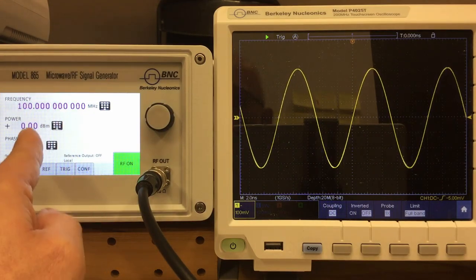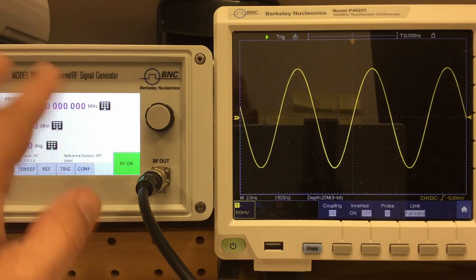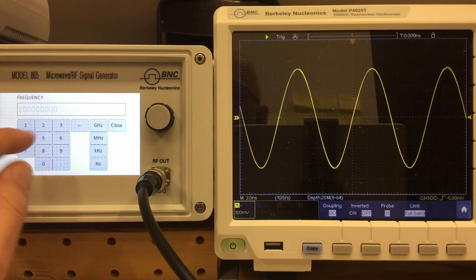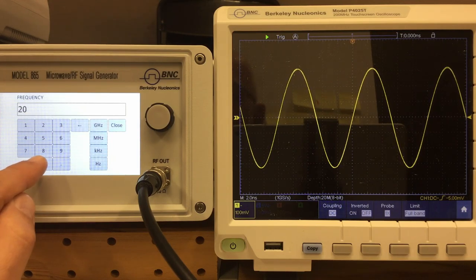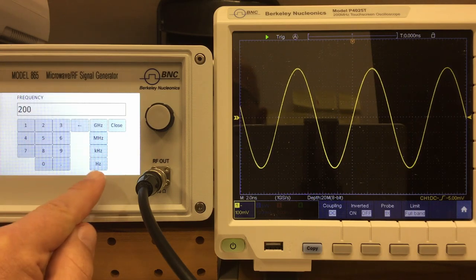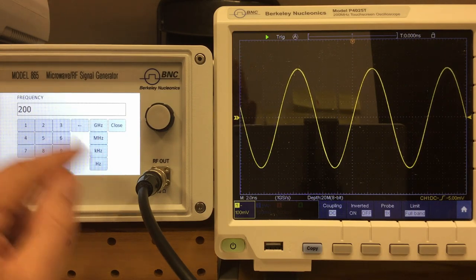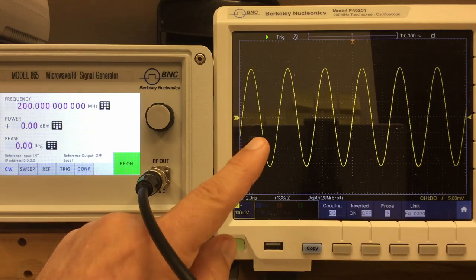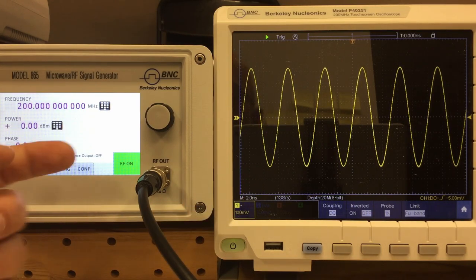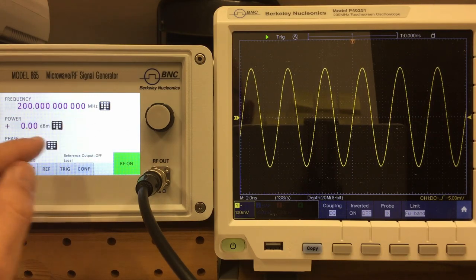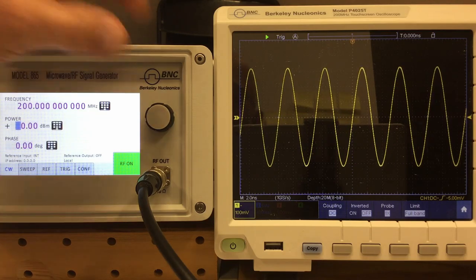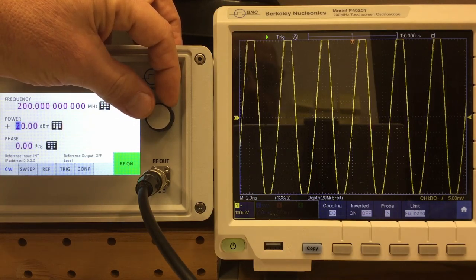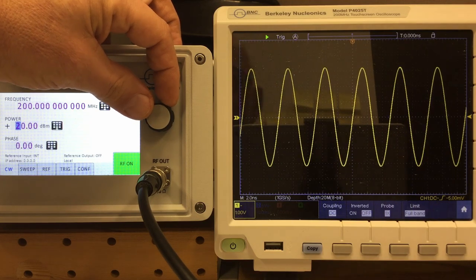The first two parameters, frequency and power, are self-explanatory. Whenever you come about such numerical parameter, you can change them either using that keypad icon and enter a new value. Usually it gives you also different units so you don't have to fumble around too much with a decimal point. Let's say we go to 200 MHz, and then we have a 200 MHz sine wave on the scope. And the second parameter, power, you can select a digit and then use the turn knob. We can go up here to 20 dBm.